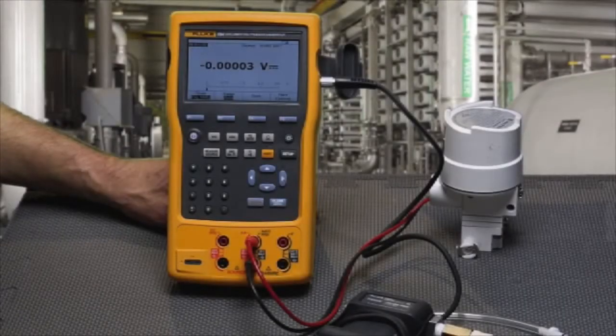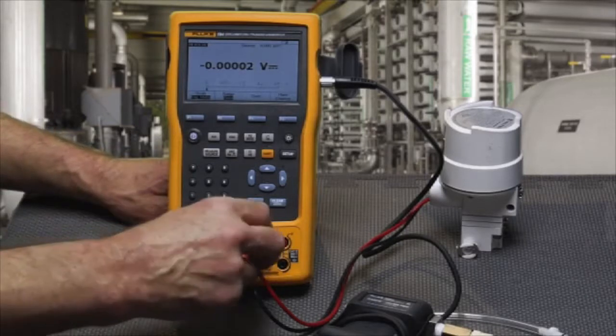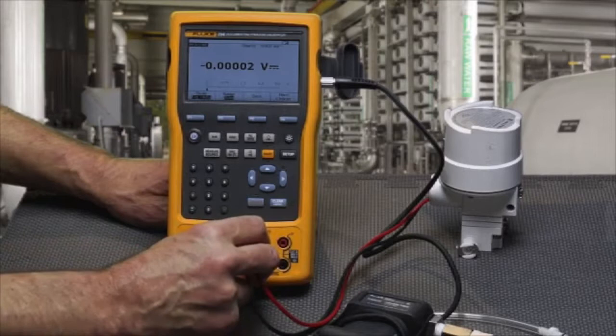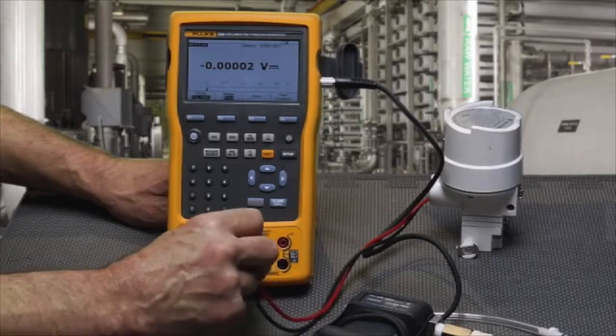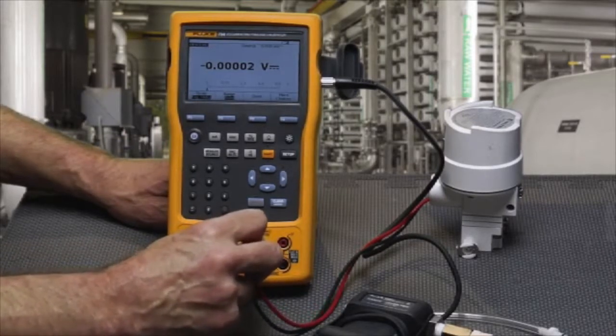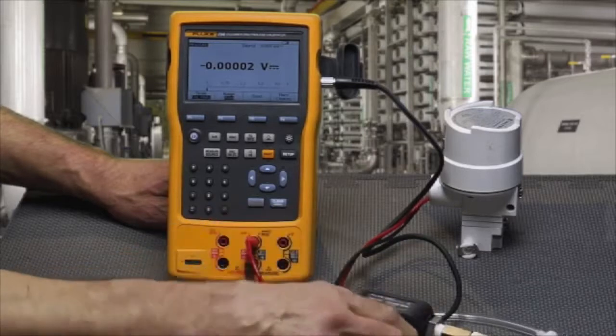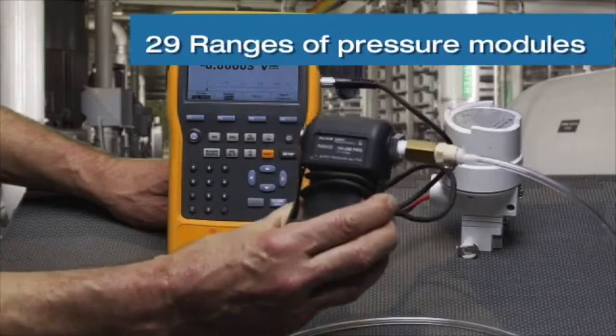Next, we're going to test an I2P converter using the Fluke 754 documenting process calibrator. We're going to apply a milliamp signal to the input of the I2P by sourcing a 4 to 20 milliamp signal from the output of the 754. We're going to measure the pressure on the output of the I2P using a pressure module.